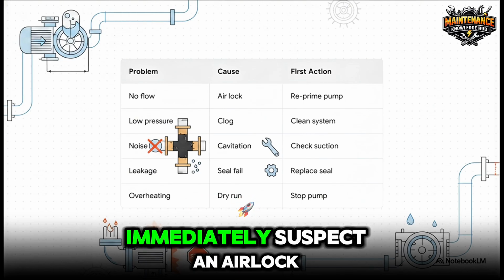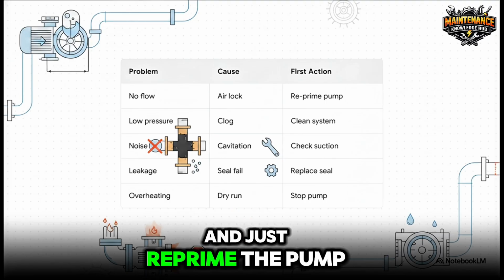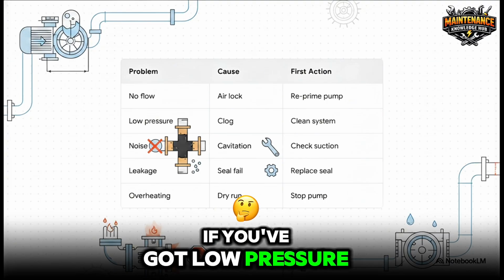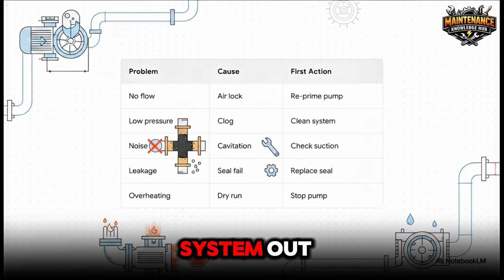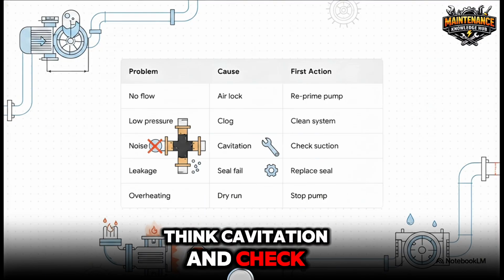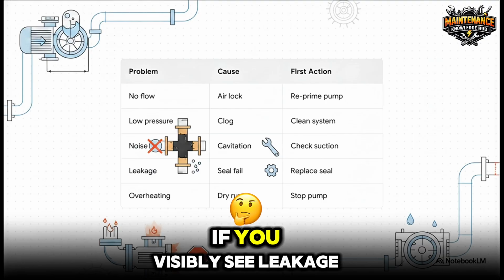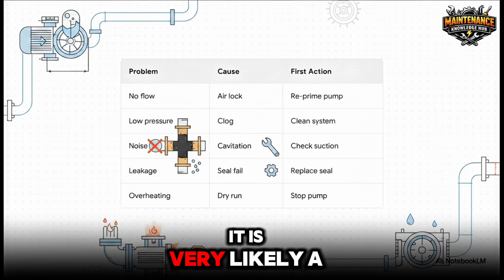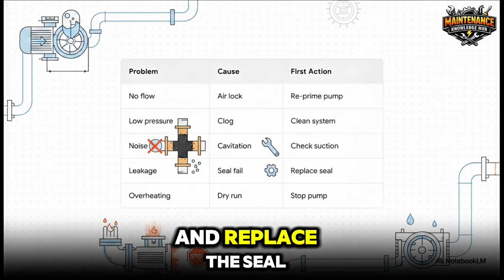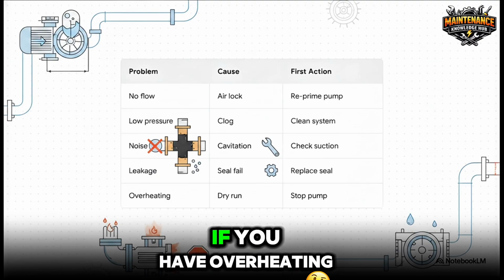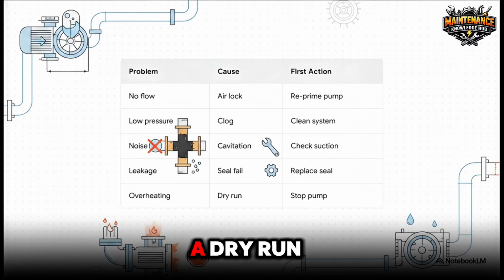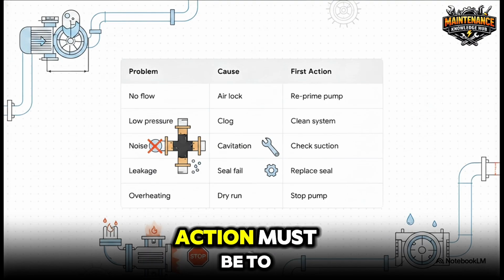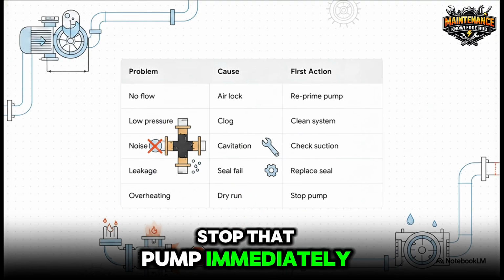If there's no flow, immediately suspect an airlock and just reprime the pump. If you've got low pressure, start looking for a clog and clean the system out. If you hear that awful gravel noise, think cavitation and check the suction line right away. If you visibly see leakage, it is very likely a seal failure, so get in there and replace the seal. And finally, if you have overheating, you might be looking at a dry run, so your absolute first action must be to stop that pump immediately.